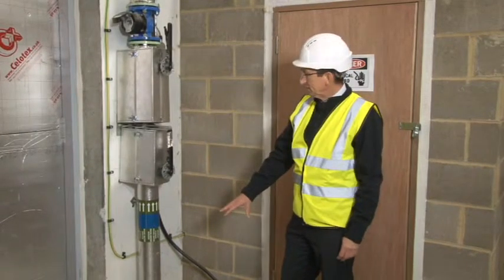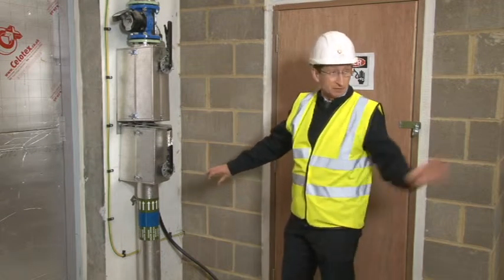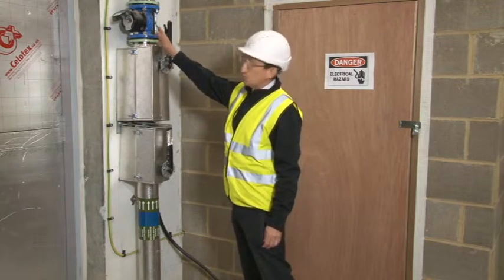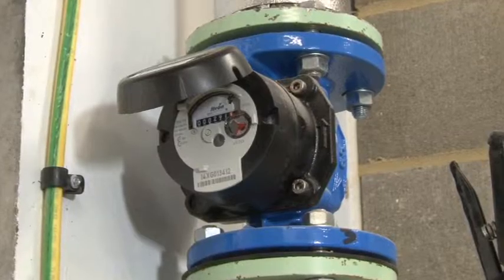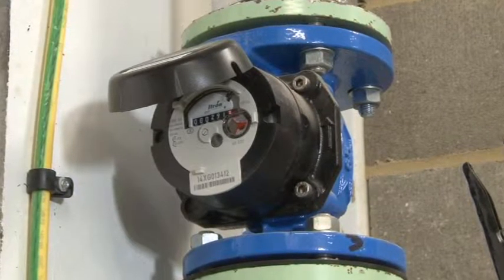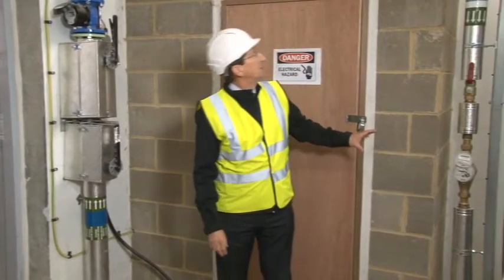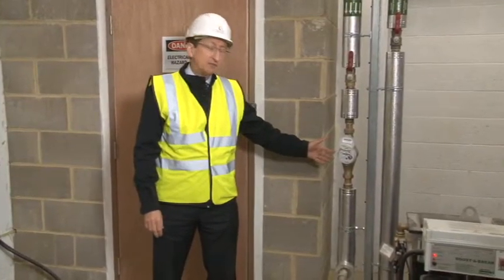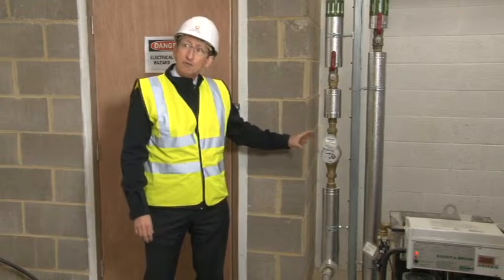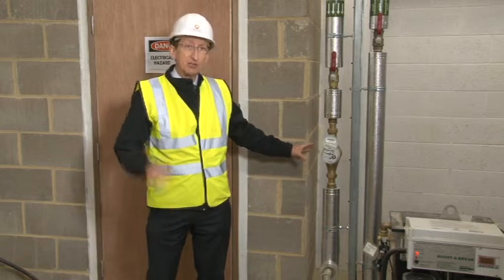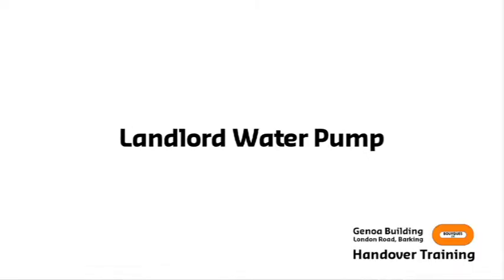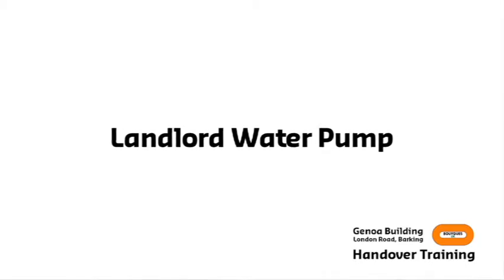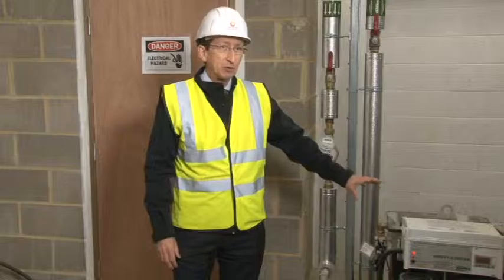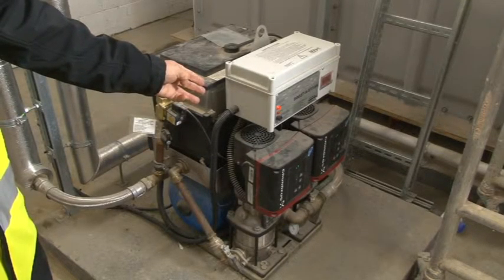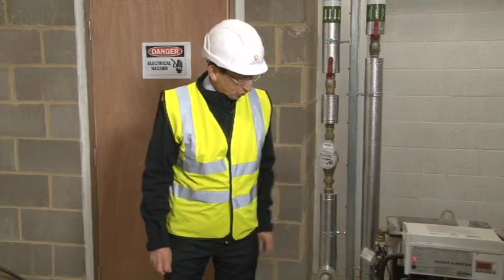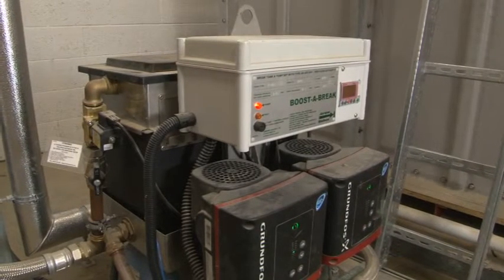So on this side of the building we've got the main incoming water supply. It's feeding the tank that we talked about earlier, and we've got the water meter here recording the water usage for the building, and that will need reading to record that side of it. There's then a secondary meter which is down here, recording the amount of water that's been used for the landlord's supplies within the building, so things like the green wall irrigation that we were talking about earlier on. And the pump set we've got here is basically a separate booster set just for those landlords' water supplies around the building in the common areas. Again, with its own internal controls, and it's a twin pump system, so we've got a duty and assist on there as well.